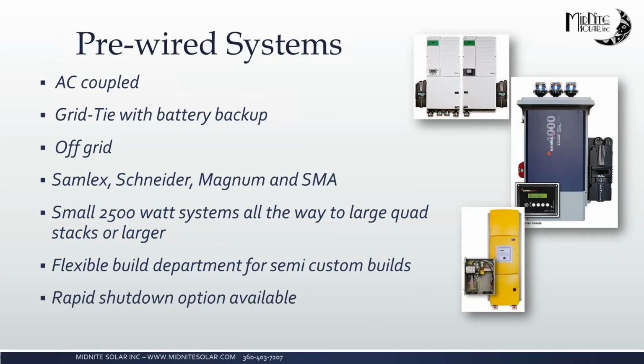Our pre-wired systems. So similar to the E-panels, the pre-wired systems come with our customized E-panels, but already have the inverter completely wired in. The charge controllers are wired in. Basically, these are ready to hang on the wall and bring in your power sources and route out to your batteries, and you're ready to go. We do AC coupled, grid tie with battery backup, and off-grid systems. Similar to what we were stating with the E-panels, we do offer Samlex, Schneider, Magnum, and SMA inverters. Everything from about 2,500 watts all the way up to the large quad stacks of Sunny Islands, which gives you 4 of their 6,000 watt inverters for a very large system.